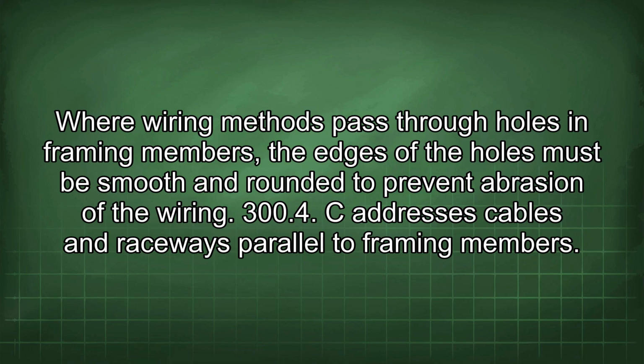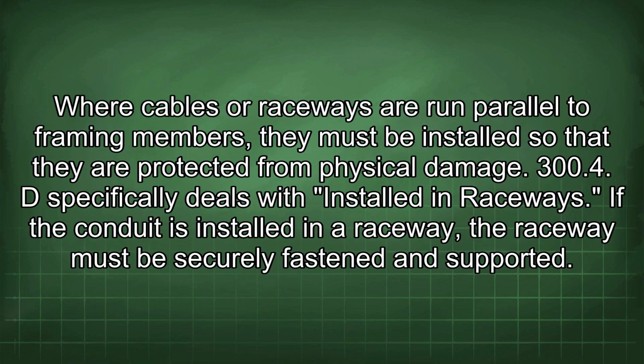300.4 C addresses cables and raceways parallel to framing members. Where cables or raceways are run parallel to framing members, they must be installed so that they are protected from physical damage. 300.4 D specifically deals with installed in raceways. If the conduit is installed in a raceway, the raceway must be securely fastened and supported.